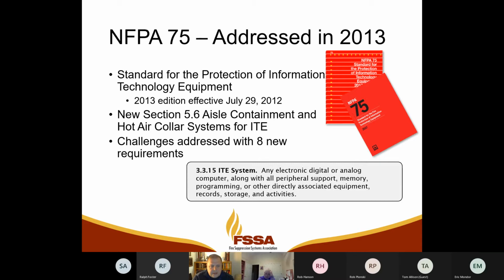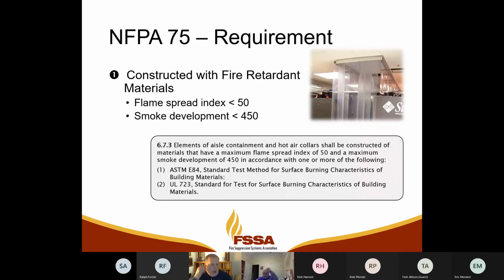If you look in 5.6, there's aisle containment and hot air collar systems for information technology equipment. There are 8 new requirements that are part of that. So we'll go over those. First off, the first requirement is that aisle containment system materials should be constructed with fire retardant materials.